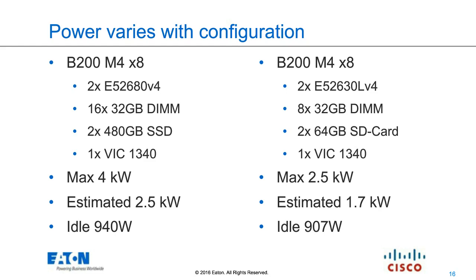We give you a second number in the Cisco power calculator, which is a rough estimate of what a typical enterprise workload will use. This is a very rough estimate and also tends to be on the high side. That rough estimate for this system would be about 2.5 kilowatts for the one on the left, and 1.7 kilowatts for the one on the right. Notice the idle numbers are very, very similar though.